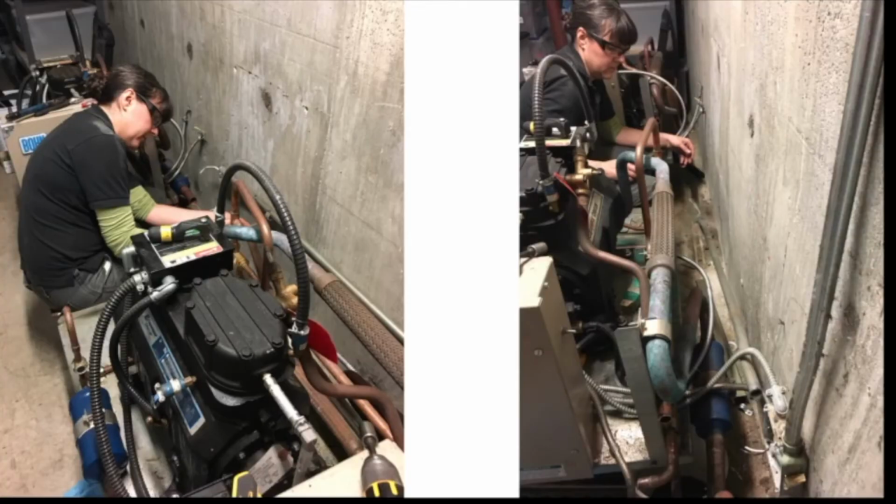In the summer, 4 floor-mounted compressors delivered air conditioning through the same air handlers. The compressors were located indoors so that there was no visible equipment outside. The noise level from these compressors made it impossible to spend any time in the basement. And they could be heard upstairs in the museum space while tours are going on. And there I am taking them apart so you could get an idea of the scale.